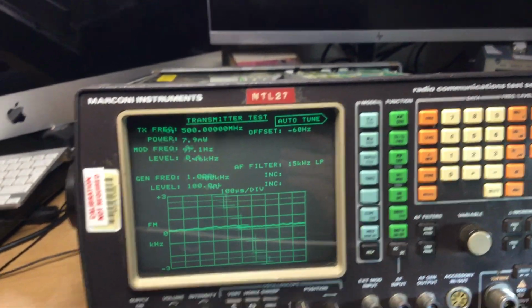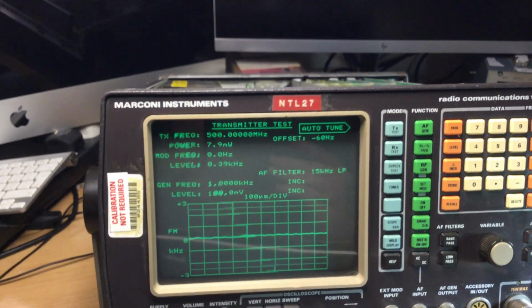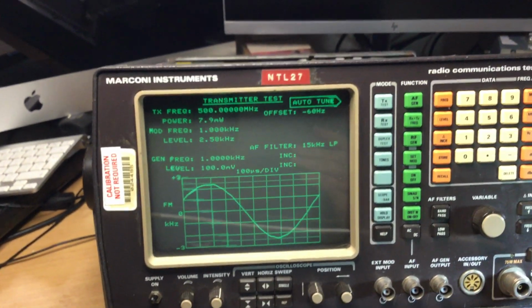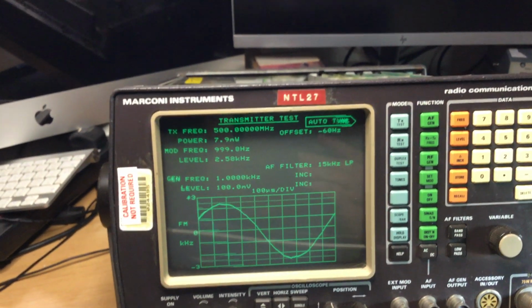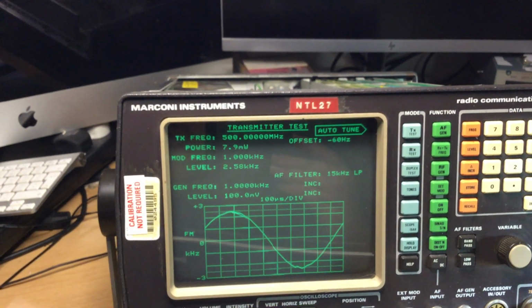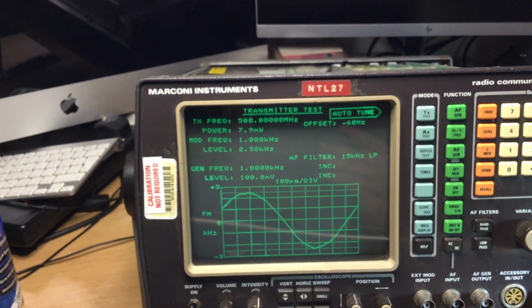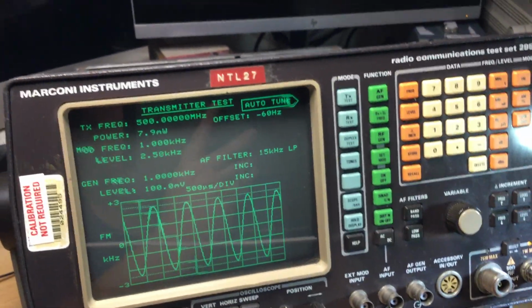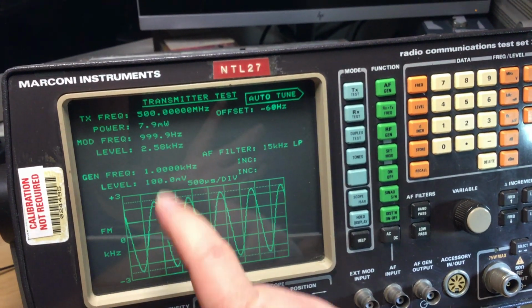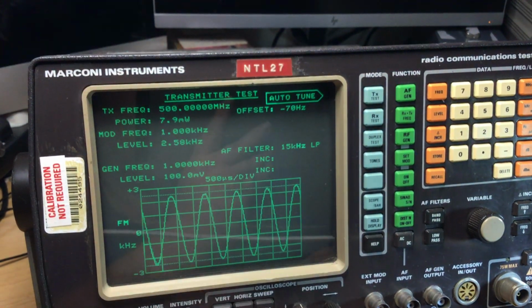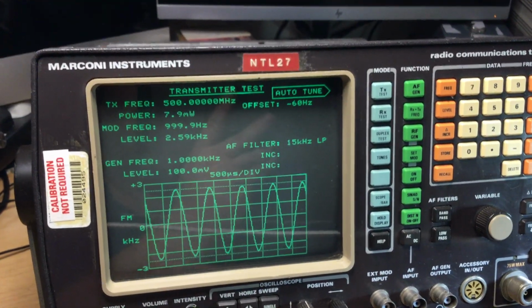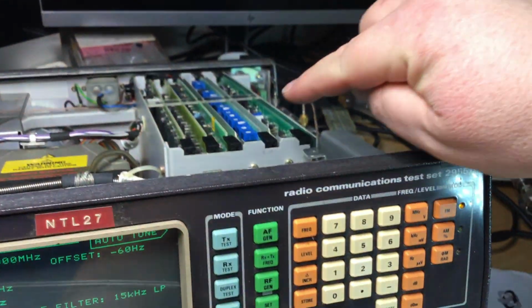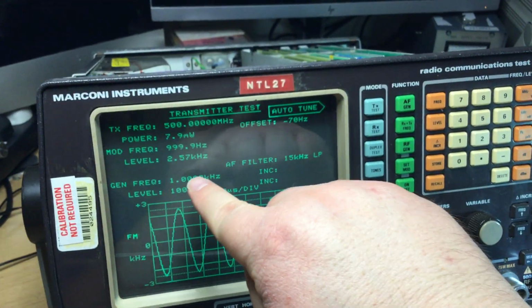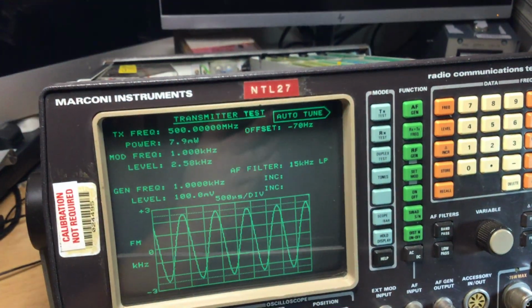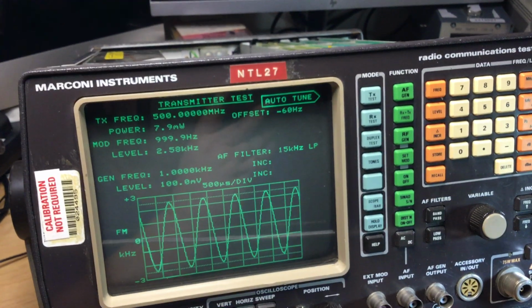Okay, well we'll put a mod on, mod gen 1 on, and we'll generate a signal. I'll just put the display mod 1 on. We're generating 1 kilohertz at 2.5 kilohertz deviation. So again, we've got a 3 kilohertz plus or minus scope, reading 2.5 kilohertz there. If you wanted to adjust that, there's a potentiometer, one of these blue potentiometers you can adjust to make sure that that reads the right level. The mod frequency is reading correctly.